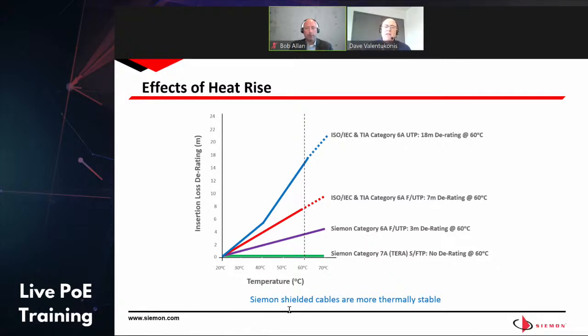If you look at these types of things, in an environment like that you would actually have to reduce your category 6A UTP cabling by up to 18 meters at 60 degrees C, which is significant in a 100 meter channel. That's about a 20% derating to address and manage that insertion loss.